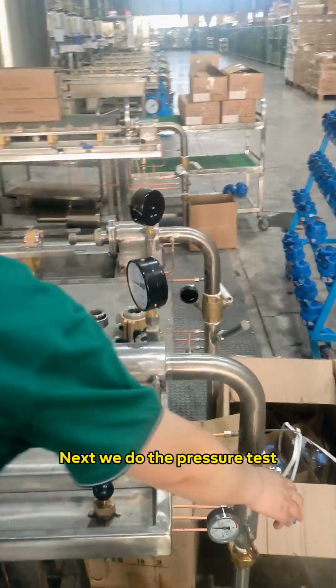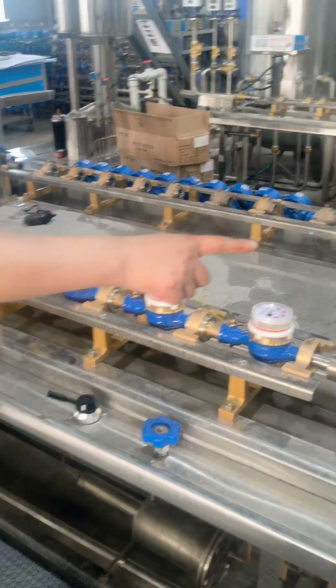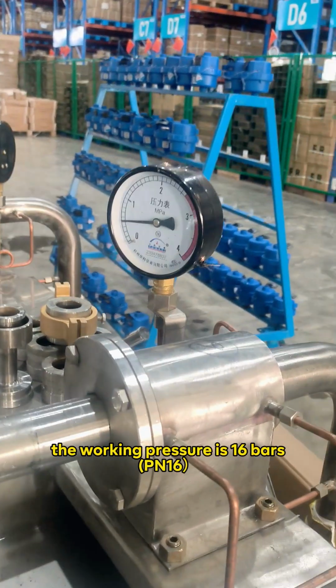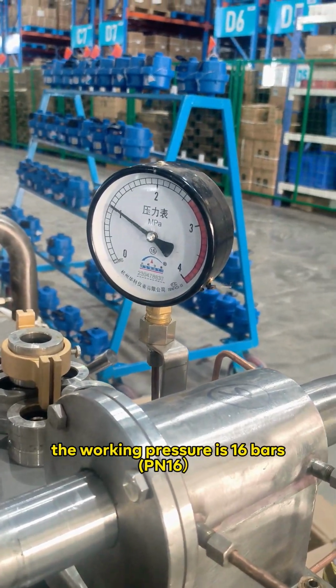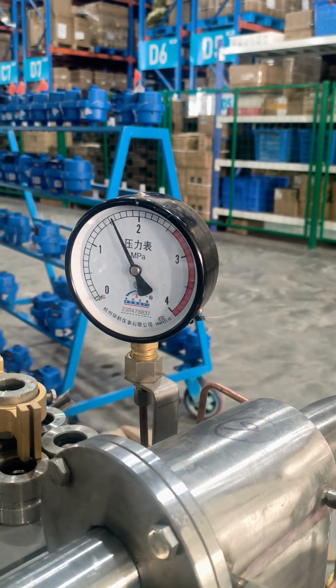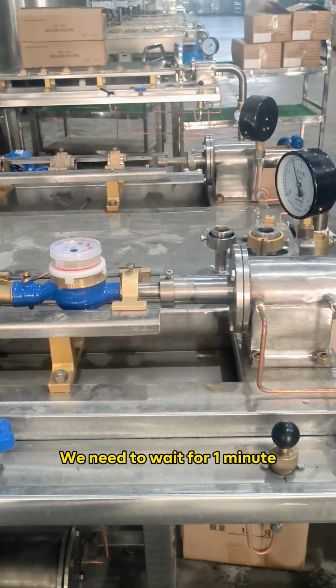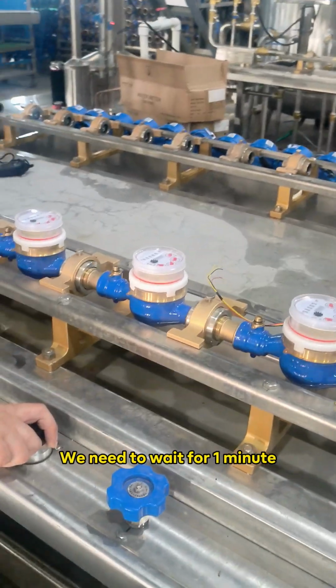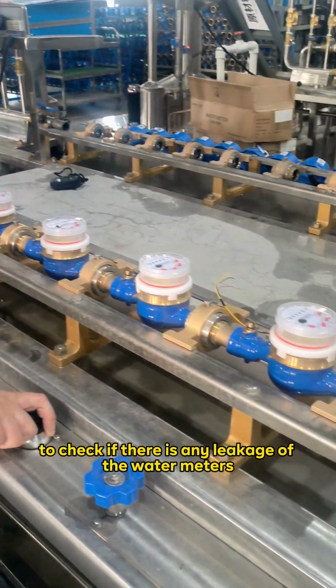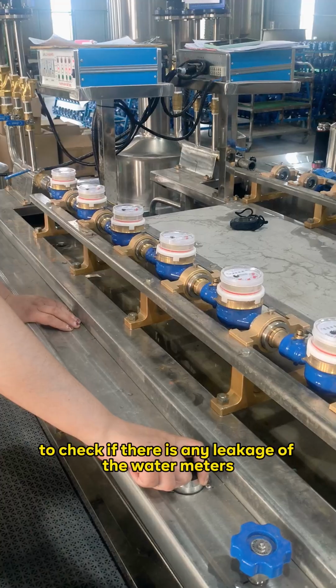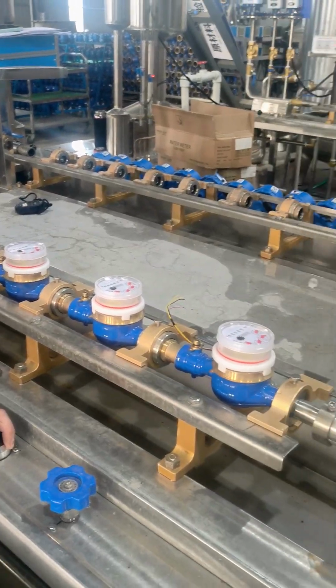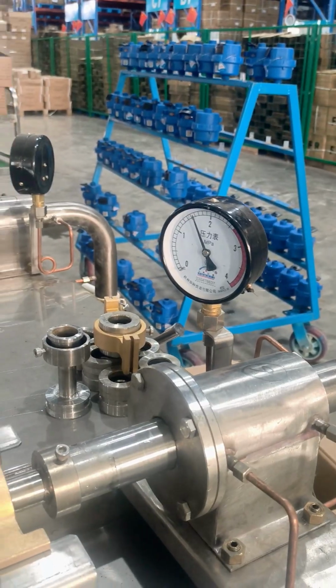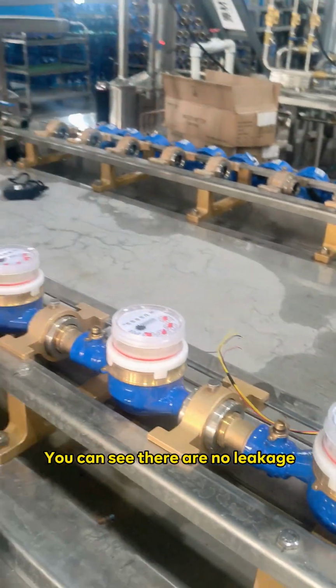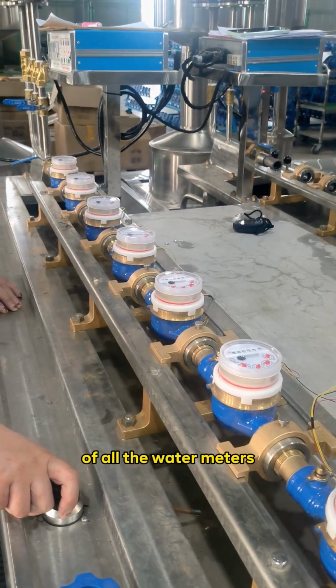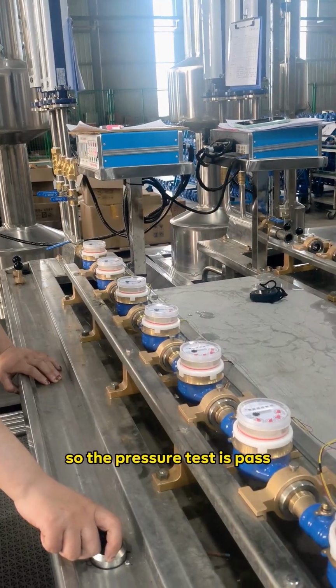And next we do the pressure test. The pressure is 16 bars. We need to wait for 1 minute to check if there is any leakage of the water meters. You can see there is no leakage of any of the water meters, so the pressure test is passed.